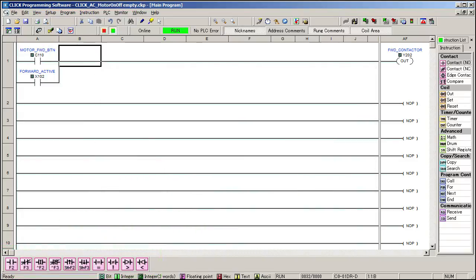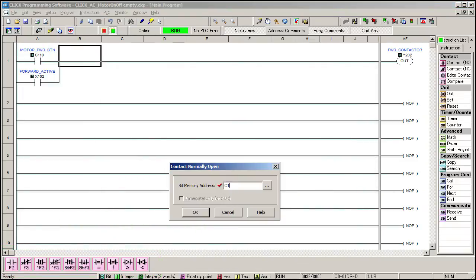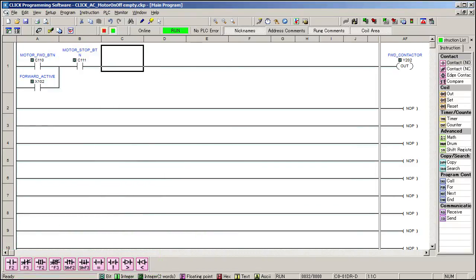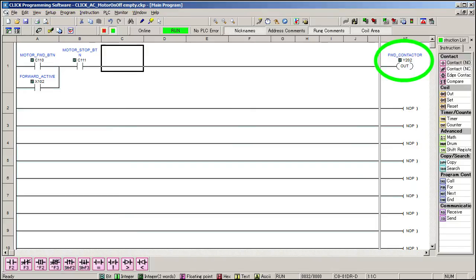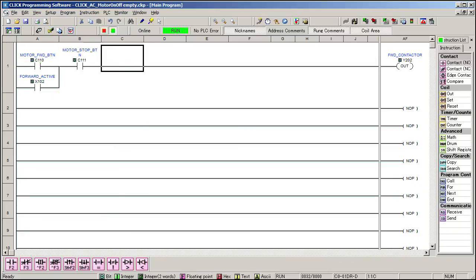We need a way to stop the motor so we'll add a stop button. Stop buttons are normally closed so this is active all the time until you press the stop button which opens this contact, which releases the contactor, which releases the AUX contact, and breaks the seal or latching action of this circuit.